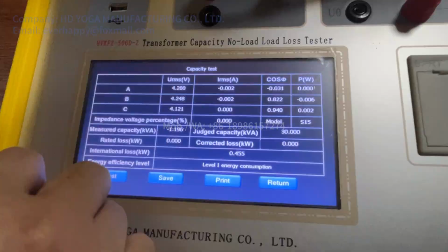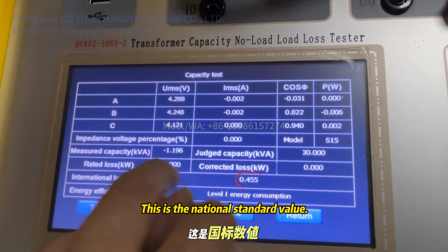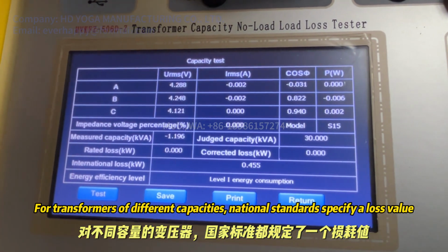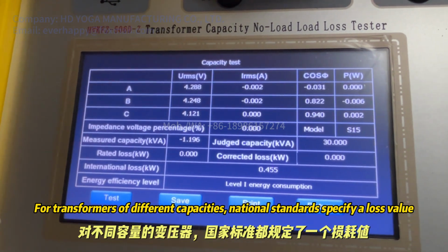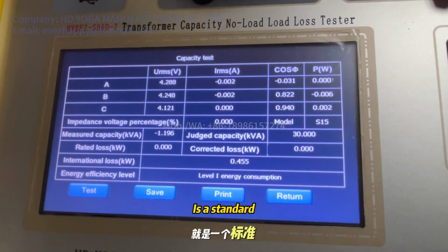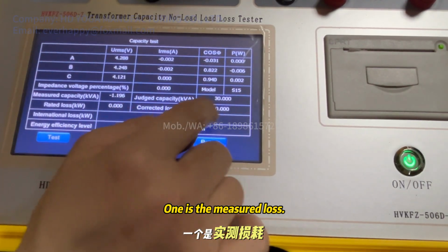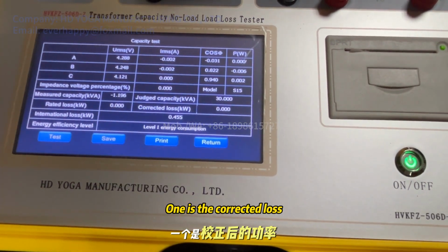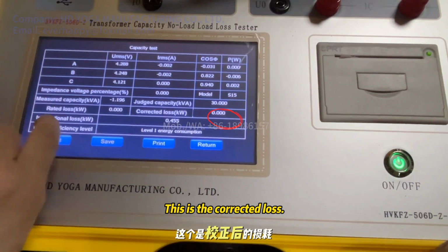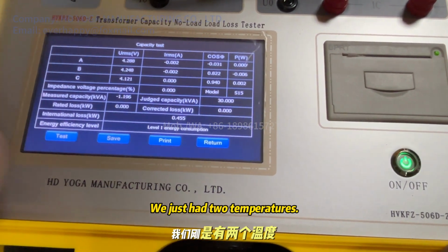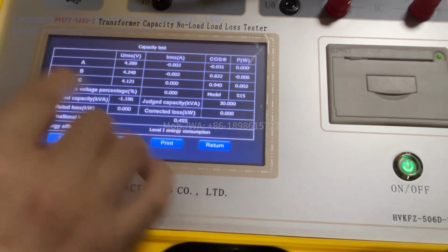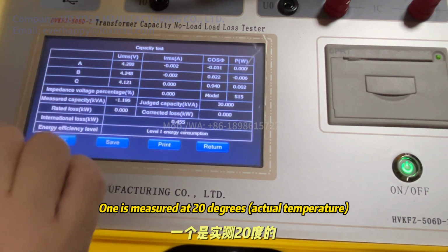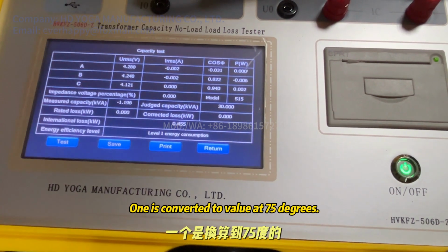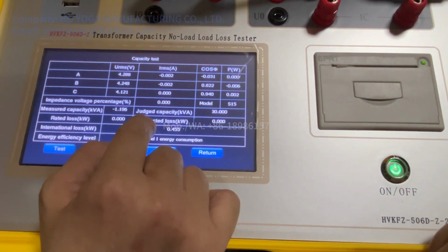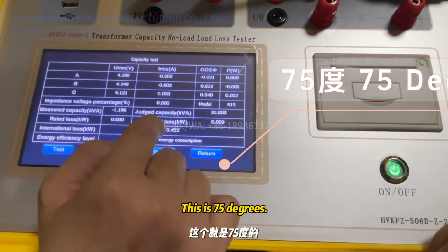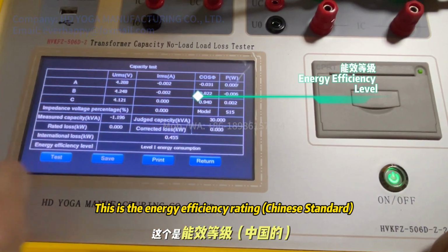Measured loss. This is the national standard value. For transformers of different capacities, national standards specify a loss value. Is a standard. One is the measured loss. One is the corrected loss. This is the corrected loss. We just had two temperatures. A 20 degree, a 75. One is measured at 20 degrees actual temperature. One is converted to value at 75 degrees. This is 75 degrees. This is the energy efficiency rating Chinese standard.